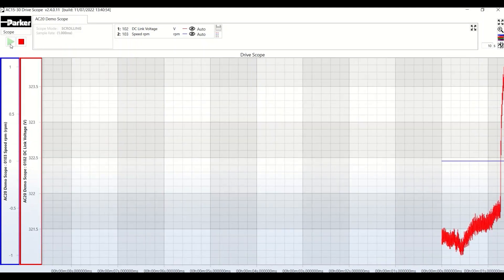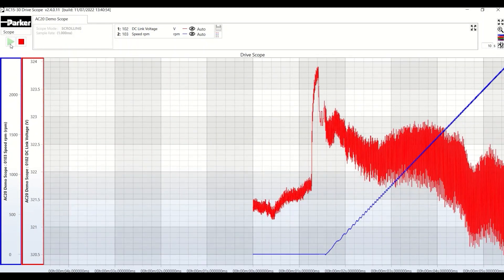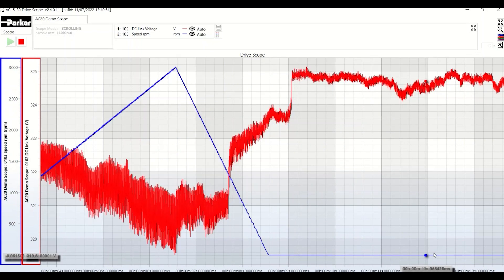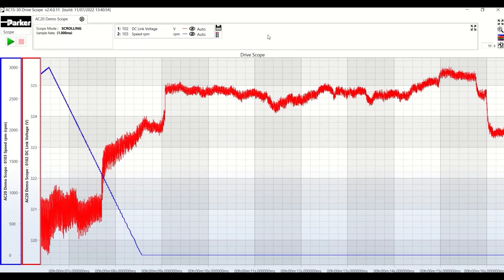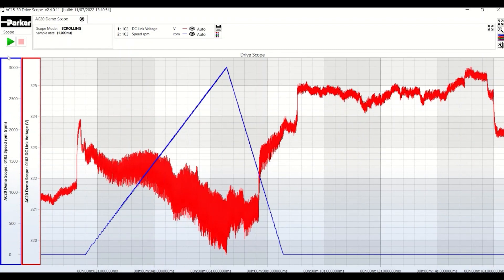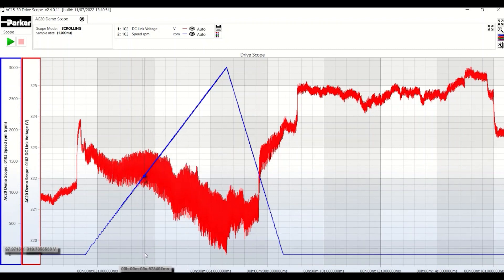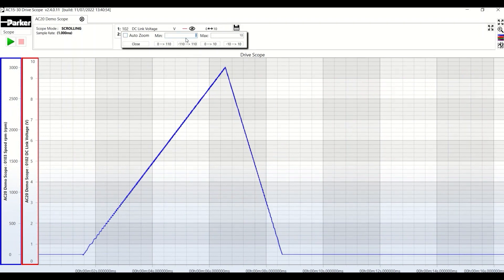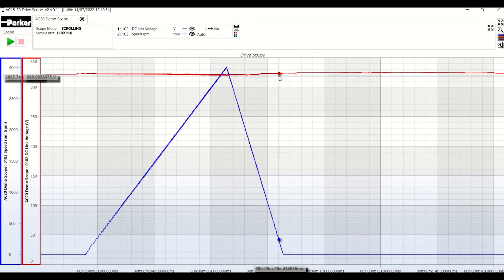I will launch the scope and start the motor in parallel in order to get some values. I will stop the motor, but leave the scope running a little. You see, I have the 10 seconds of data which are displayed, but if I stop the scope and click on this icon, I will see all of the data between the start and the end of the recording. What we can see is that the DC bus had a lot of noise, but that doesn't mean a great deal since we are in auto scale mode. On the red channel, or channel 1, we are between 320 volts and 325 volts, which is not particularly useful for us.